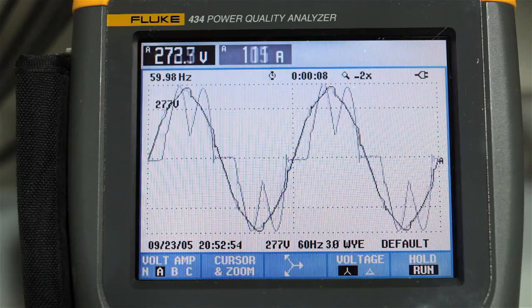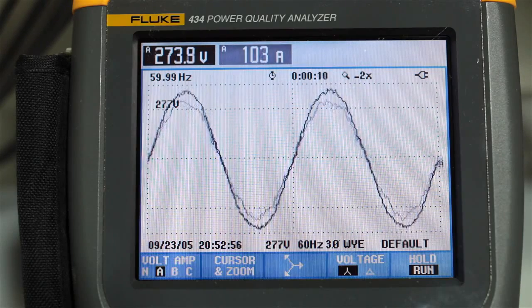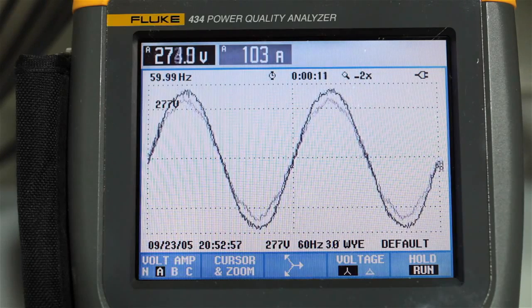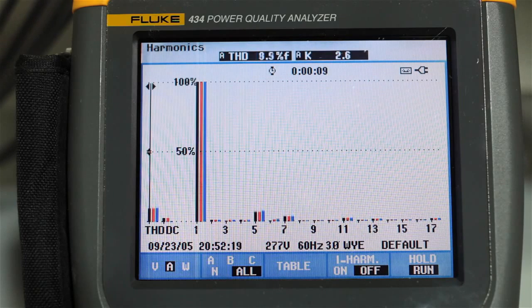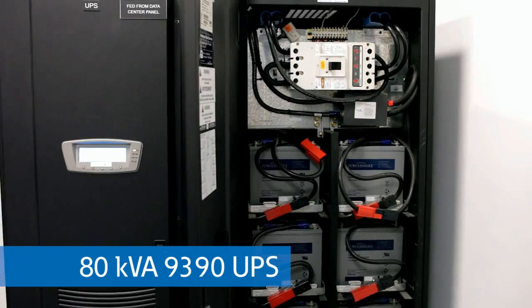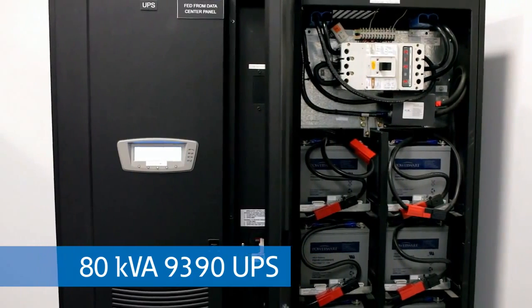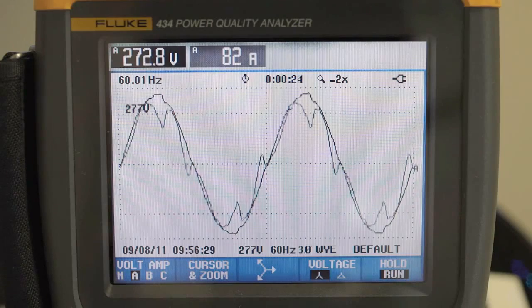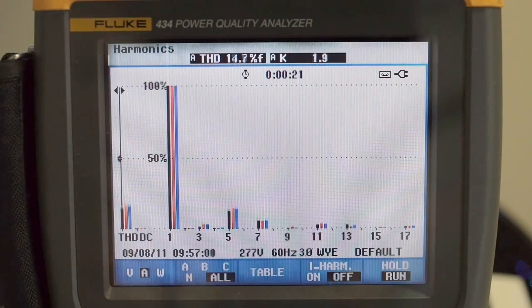However, active harmonic filters are one of the most costly solutions. Active harmonic filters continuously monitor the non-linear load and filter as necessary. Our 9390 and 9395 UPSs feature an active rectifier built into the equipment, allowing continuous active harmonic correction.